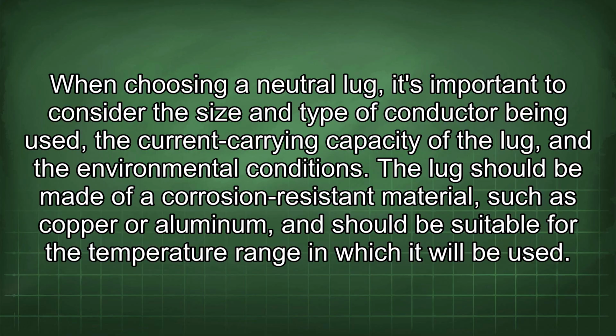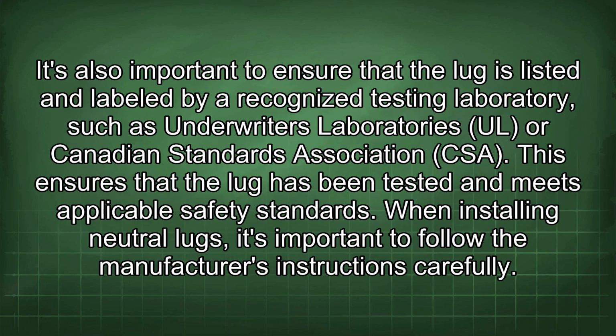The lug should be made of a corrosion-resistant material such as copper or aluminum and should be suitable for the temperature range in which it will be used. It's also important to ensure that the lug is listed and labeled by a recognized testing laboratory such as Underwriters Laboratories (UL) or Canadian Standards Association (CSA). This ensures that the lug has been tested and meets applicable safety standards.